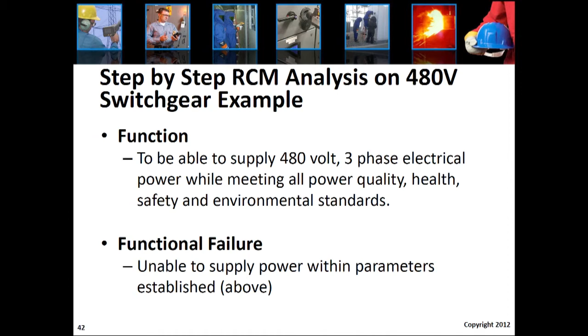Failure modes: the door gaskets leak due to embrittlement, wiring fails due to loose connections, bus bar control wiring or terminal connections fail due to insulation breakdown, fuse clips loosen due to physical damage.